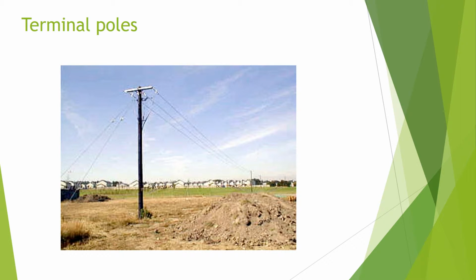Terminal poles are used near the ends of the line. Normally, the underground cable supplying the line will break ground at the base of the pole and run up it, secured by cleats, to an external cable termination. Jumpers then connect the termination to the line conductors. The crossarm used on the terminal pole is similar to that used on a section pole, but with only one set of strain insulators per phase.